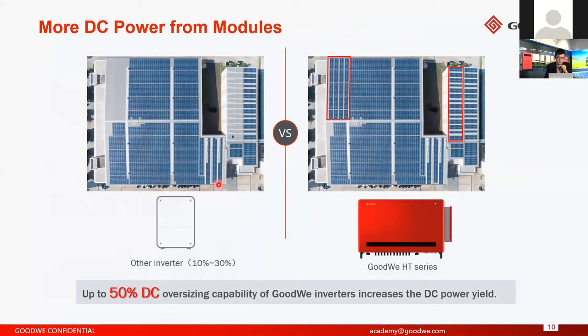Here is more DC power from the modules. For our product, we support a maximum of 50% DC oversize capacity. That means, for example, if the inverter is 100 kilowatt, on the DC side you can connect a maximum of 150 kilowatt. Because DC oversize is now very popular in a lot of countries. If you connect more panels on the DC side, you can save some investment on the whole system. That's why more and more customers want more DC oversize. For our HT series, we can support a maximum of 50% DC oversize, but for other brands, I think it's around 10 to 30%.